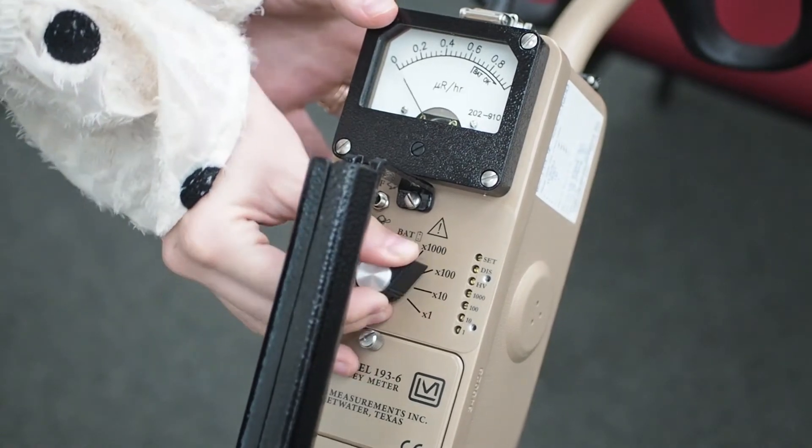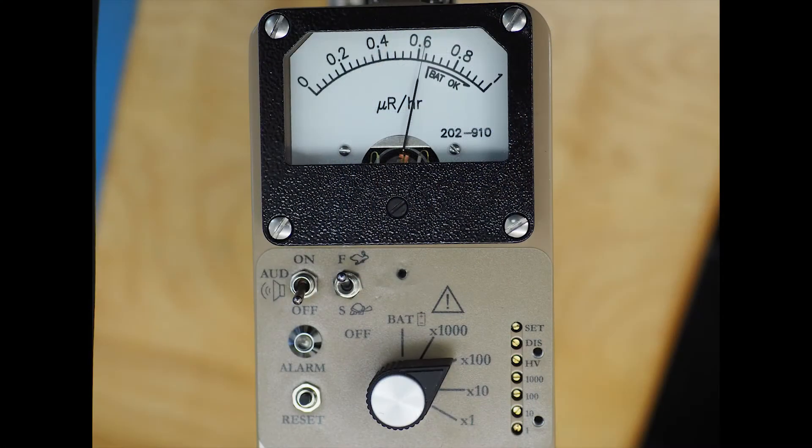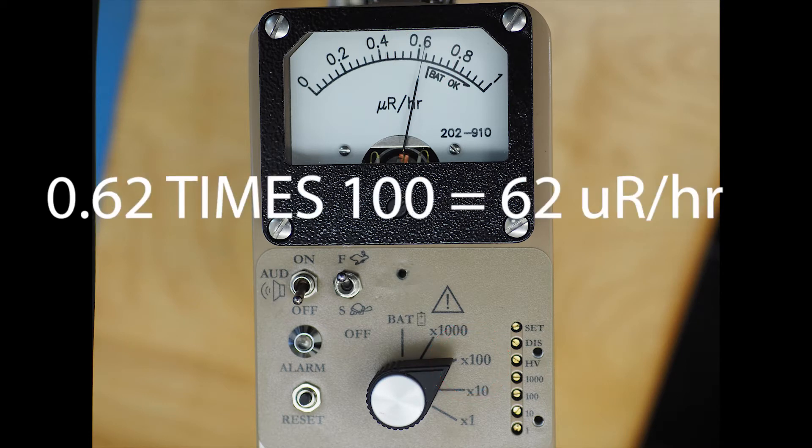Move the range selector switch to one of the range multipliers to make a measurement. To determine the actual reading, multiply the scale readings by the range multiplier. In this picture, the needle is on the 0.62 mark and the knob is on the x100 position. So the actual reading is 0.62 x100 or 62 µR per hour.